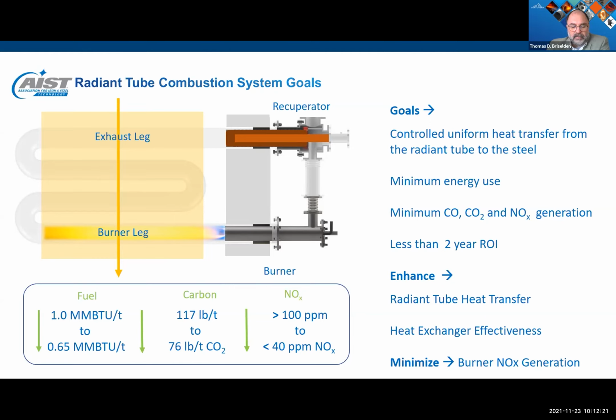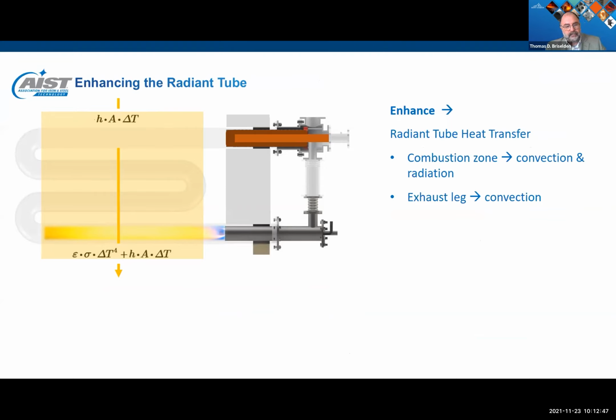So with all of this in mind, we want to emphasize the radiant tube. We want to enhance the radiant tube heat transfer, improve the heat exchanger effectiveness, and simultaneously reduce NOx. While this sounds trivial, several of these statements can be contradictory. As an example, increased efficiency can require higher levels of preheat air, which, if not managed properly, can increase NOx. The unique issue enhancing the radiant tube heat transfer is that the burner leg utilizes both convection and radiation heat transfer from the flame. When the combustion process is complete, in the third and fourth legs, the exhaust gas loses nearly all of its radiative properties. Thus, convection is the primary means of heat transfer and is lower than that of the combined. So how do we make the exhaust leg look like a burner leg?